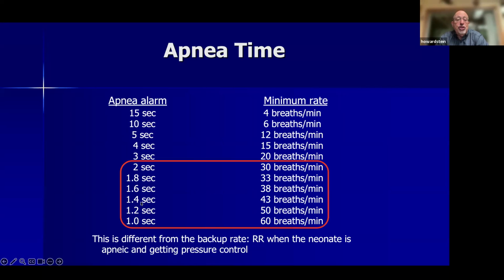We typically use this range over here, between 2 seconds and 1 second. And here you can see the corresponding rates. And when I set my backup rate, which is the rate the baby's going to be ventilated at when they stay apneic, I usually try and match it. So if I have the baby on backup settings with a rate of 30, I'll put them on a 2-second apnea time. If I'm all the way up to 50, I'll use a 1.2 apnea time, so that I'm just using one concept of backup rate.